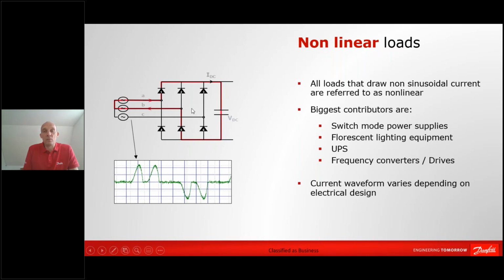The way that the current goes into the frequency converter, the way that the diodes are conducting, means that we are not pulling sinusoidal current from the grid. For the current to go into the DC link, the voltage on the input side needs to be higher than the voltage on the DC side. And that means that we only have a very narrow window of time where this behavior is in place. And that basically means that the current that is pulled from the supply line is a pulse form that you can see below the picture here, the green curve here with 2 positive pulses followed by 2 negative pulses.